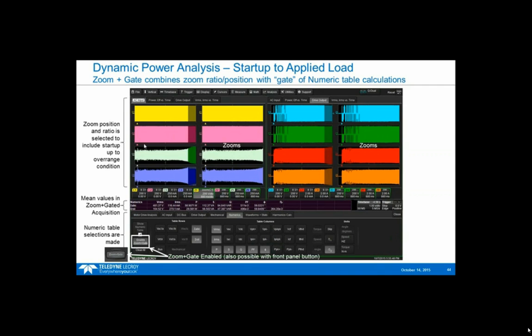We have a capability called zoom and gate, so we're going to gate the acquisition to the area right up to the point where I've overdriven the amplifier a little bit with this current signal. We've basically selected a zoom position and ratio, and it's variable, so I can make it infinitely variable and look at just this particular area. Now I'm in zoom and gate mode, and the mean value is calculated just on this gated area, which is why we call it the zoom and gate mode.